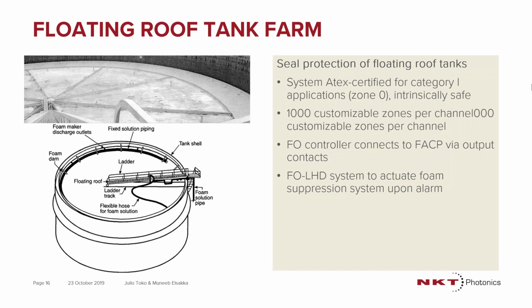One example would be the floating roof tank farm. For instance, normally what we do is seal protection, so you make sure that you have an ATEX certified system, so there is zone 1, zone 0, intrinsically safe. One advantage of fiber optic is, as we said earlier, it's immune to EMI, and also we don't have an active current going through it like a traditional linear heat detection. Because we have a passive device, this unit is perfect for petrochemical areas where there are a lot of restrictions in terms of explosion-proof areas. So one example would be to run the fiber optic linear detection on top of the roof, right by the seal.